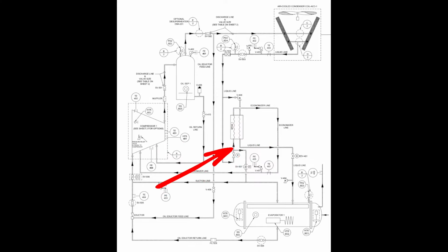So the goal of this economizer is not to flash off the liquid refrigerant going to the evaporator, but it is to increase its effectiveness by removing more enthalpy. Again, we don't have to get crazy off into that if you don't want to. I'll just throw the words out there, and if you have questions, feel free to ask them. Ultimately, what I'm saying is we make the refrigerant do more work by increasing its subcooling. So let's say, just to give you some ballpark numbers, let's say we had 10 degrees of subcooling coming into this braze plate. We may have 20, 25 degrees or so leaving this braze plate, something to that effect.